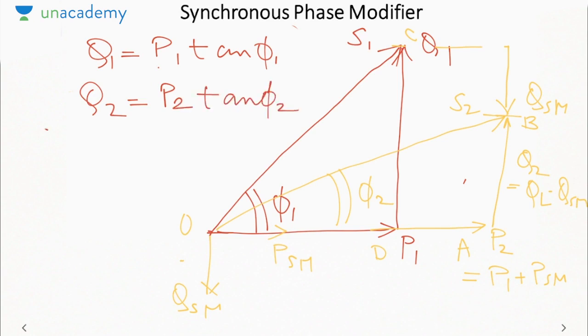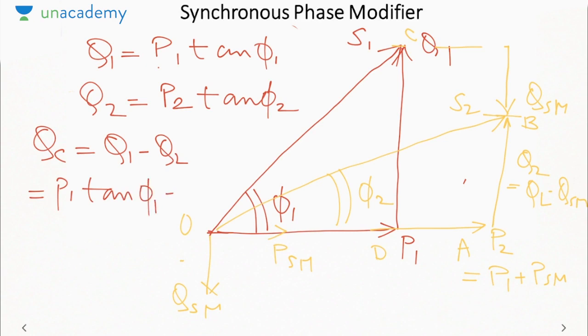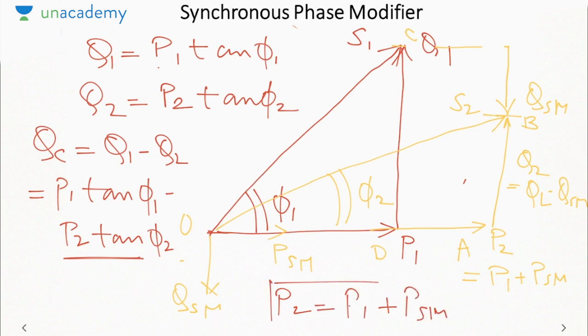So that means QC, which is equal to Q1 minus Q2, will be P1 tan phi 1 minus P2 tan phi 2. That will be the reactive power rating of the capacitor. And here P2 is equal to actually P1 plus PSM. PSM is the real power absorbed by the synchronous motor.